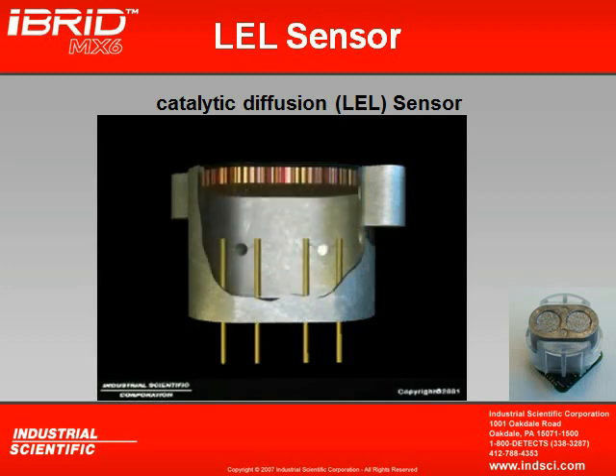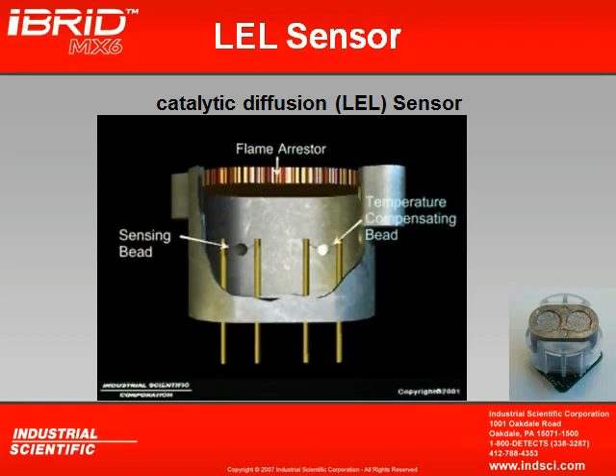If you could see the inside of a combustible sensor, this is what you'd see. You've got these two little tiny beads inside. One's a sensing bead, the other one's a temperature compensating bead. Now these two beads are manufactured with 1/1000th of an inch thin platinum wire that's spun like a coil or like a filament in a light bulb. We then put chemicals on these beads. The sensing bead is doped with 11 different catalysts to give it the ability to burn combustible gas, whereas your temperature compensating bead is coated with a material to make it blind. It can't burn combustible gas.